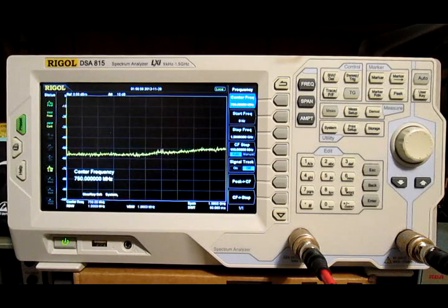However, it doesn't mean that you couldn't still use it for a signal source for troubleshooting, et cetera. So what I'm going to show you is a way to get a fixed frequency out of the analyzer and use that for a source.